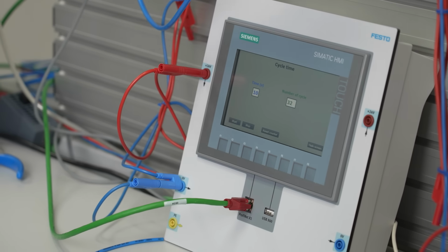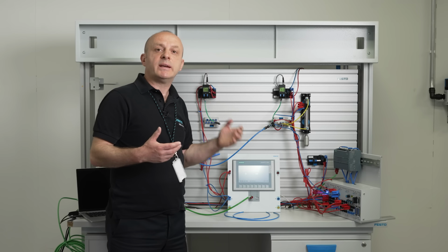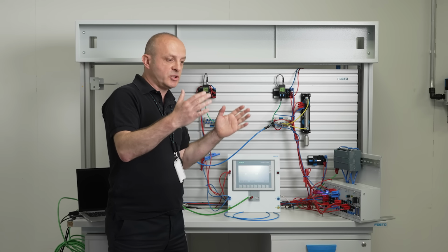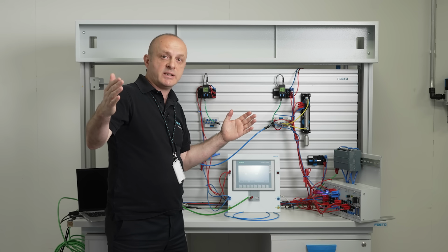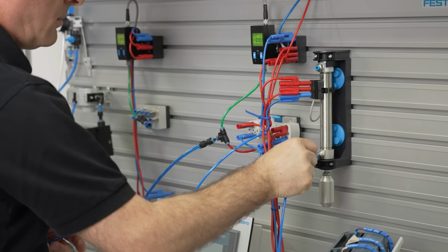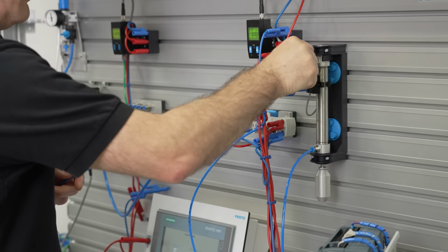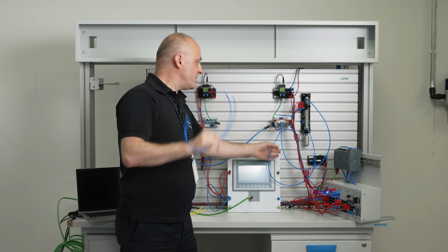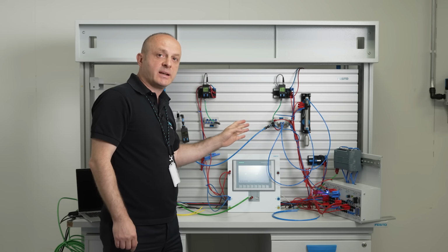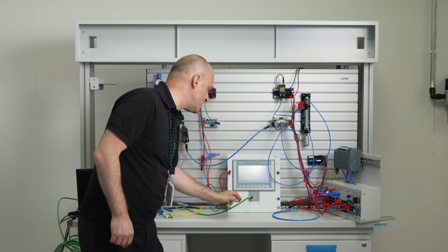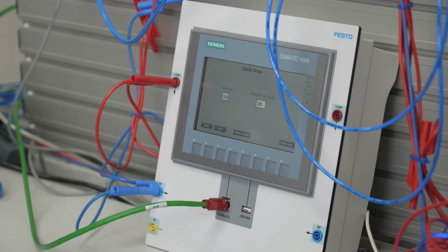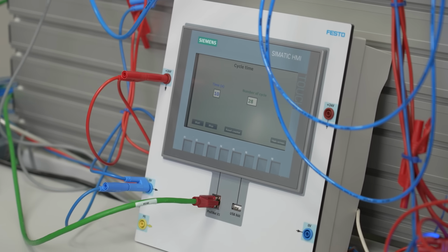Now I will replace the tubes with longer ones, simulating that they've been damaged, we need to replace them, but unfortunately we replace them with longer ones without realizing. The longer tubes can cause some issues, we will have a look. The tubes have been replaced with the longer ones. I will run the machine for 10 seconds and see how many cycles we can run. In 10 seconds, the number of cycles is 28. With the shorter tube, it was 32.